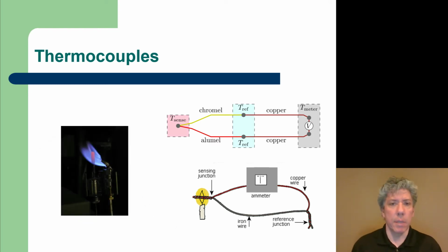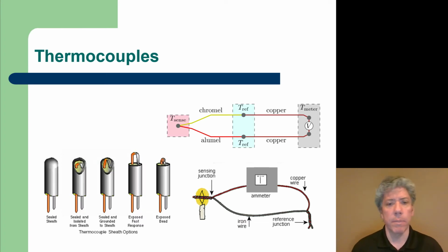Now, thermocouples have very wide temperature sensing ranges. Many thermocouples can withstand flame temperatures. These are just metals, and as long as the metals don't melt and don't go too far out of range, the metal can sense very high temperatures. Now, there is a trade-off. Thermocouples aren't known for their accuracy. They're fairly repeatable, but they're not all that accurate, and so calibrating them is very important if you want to get reasonable results from them.